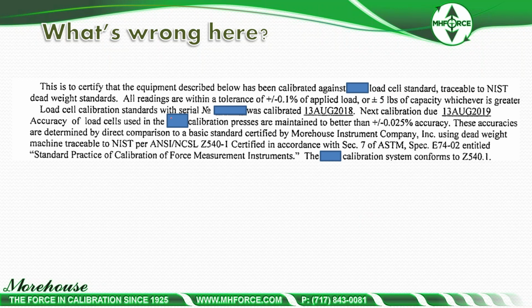So essentially, ASTM spec E74-02. Wow, that hasn't been updated in a long time. And this is a recent cert. Look, it's due August 2019. This was calibrated in 2018. The ASTM standard they're referencing is E74-02, which now we're at E74-18. There was an E74-04, an 06, a 13. This company is just non-compliant at all. And basically they're saying, hey, we go to NIST. We go to NIST, right, through Morehouse, but Morehouse doesn't do our cal. A customer of Morehouse does our cal, and we're way down here.